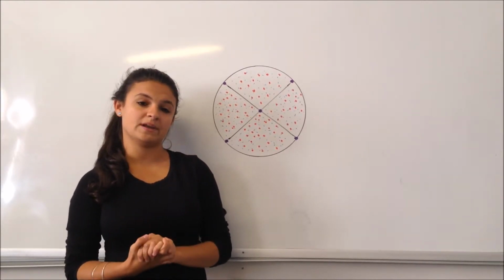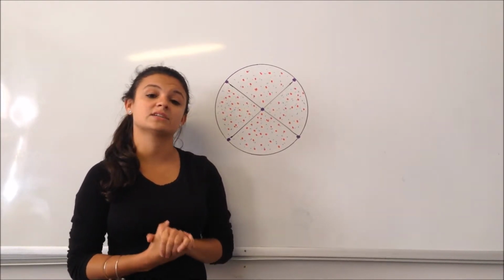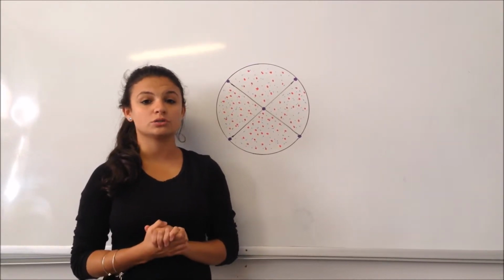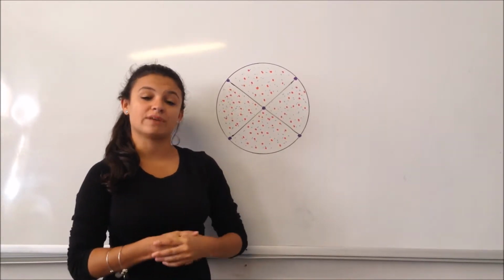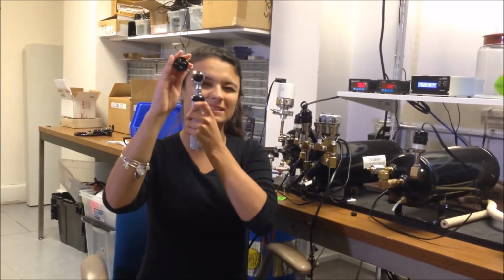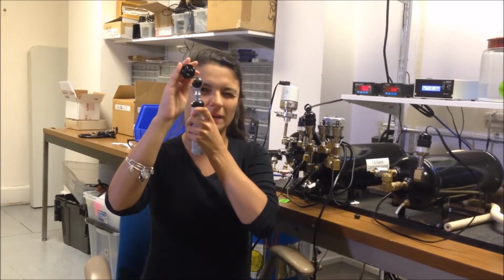the thermocouple element from the surrounding gases, and this could lead to incorrect readings. Contaminated tubes are also slow to respond, and the readings grossly over or undershoot the expected results. You can check and see if your thermocouple tube is contaminated by performing a visual test using an otoscope to see if there's an oil pool at the bottom of the tube.